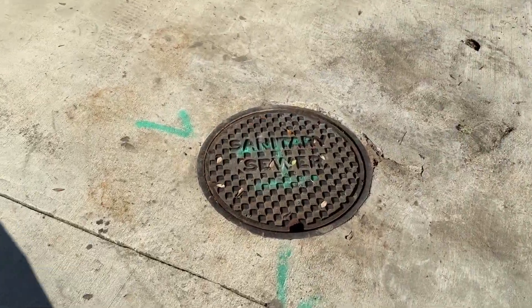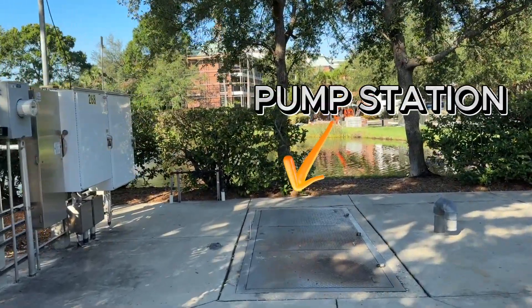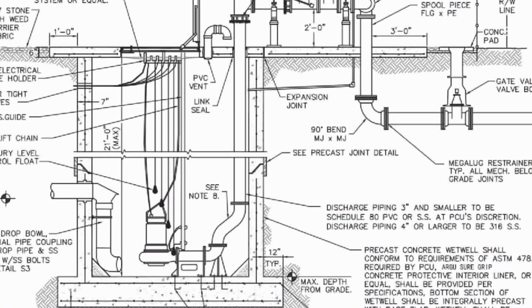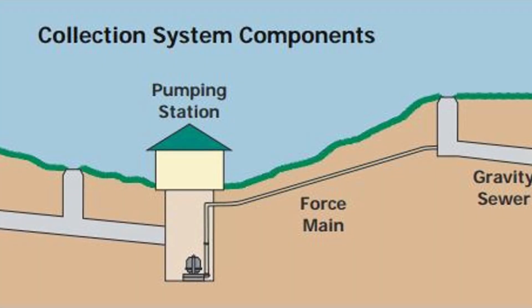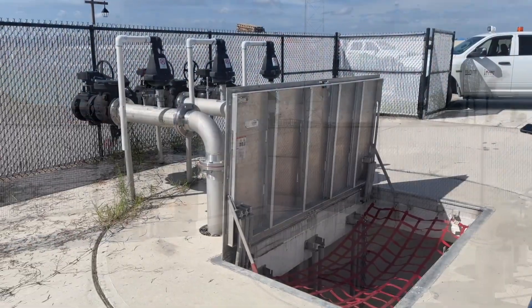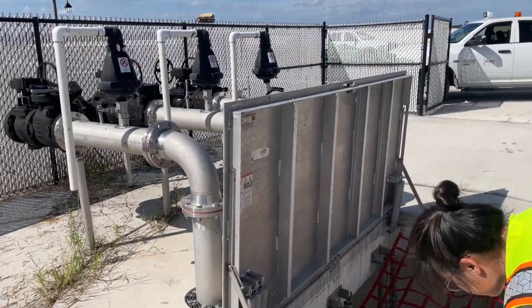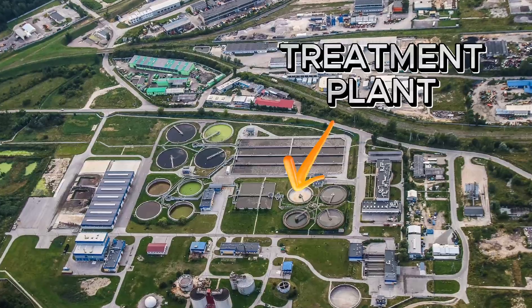So what do we do when gravity doesn't make sense? Time to introduce a pump station. A pump station, also called a lift station, is basically a pit where wastewater collects. Once it hits a certain level, pumps turn on and push it through a pressurized pipe called a force main. That force main moves the flow uphill or across flat terrain until it can rejoin a gravity system. Here's a real layout from a past project — sewage collects within the manholes, flows through the station, and gets pumped out to the nearest existing gravity main or force main, depending on how the system is set up. All this wastewater then goes to a wastewater treatment plant, where the sewage gets treated and put back into the environment.